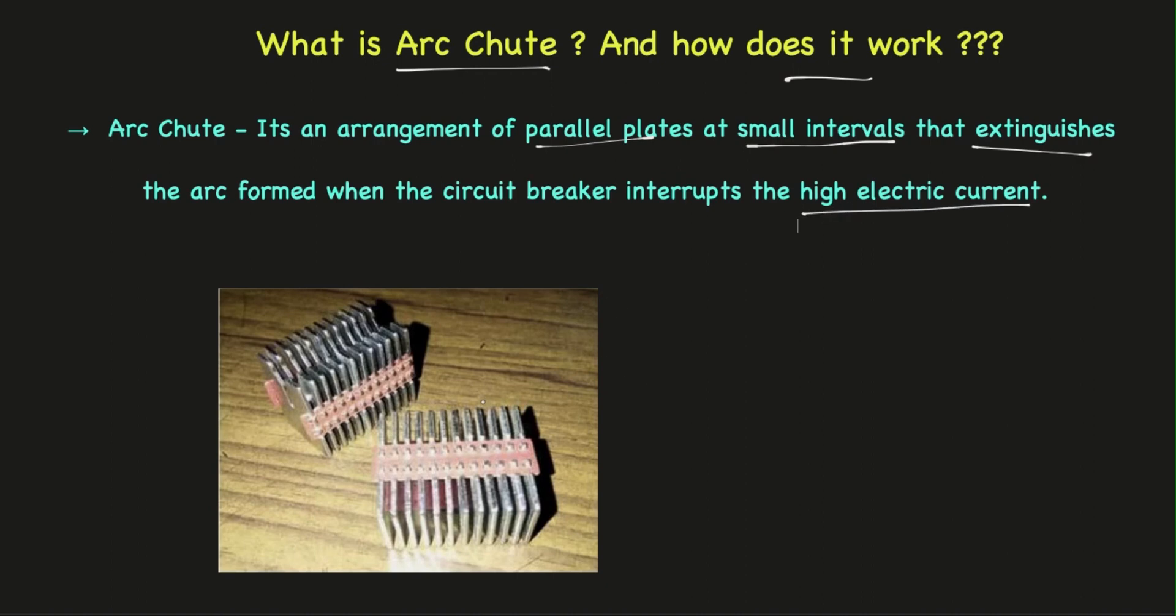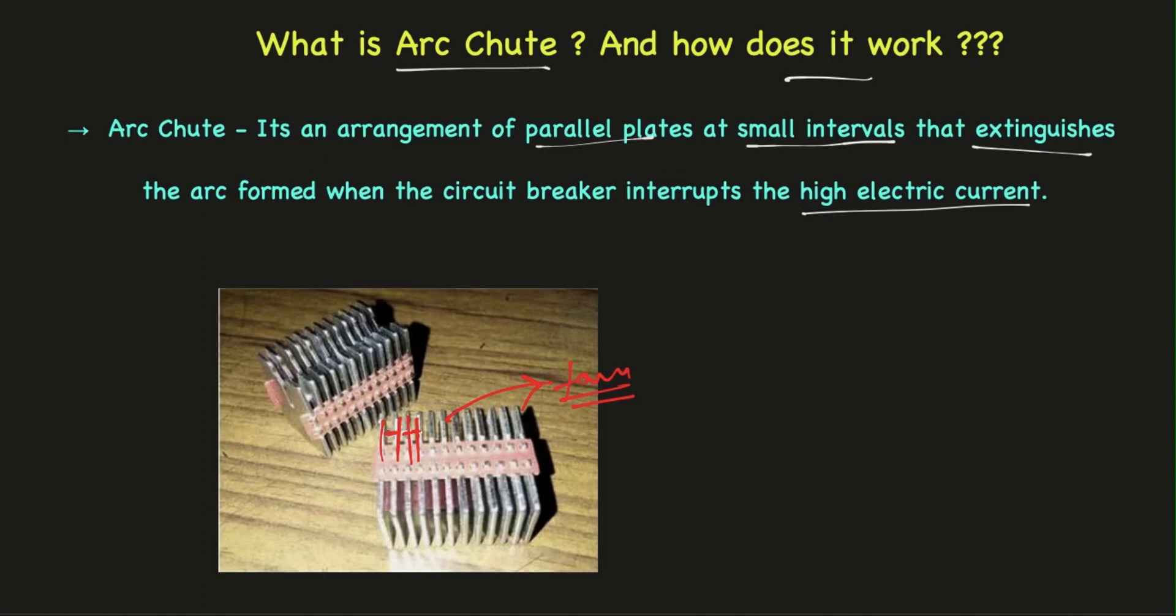This is how externally arc chutes look like. These are the small metallic plates which are separated from each other, and these metallic plates are made with ferromagnetic material so that when an arc is formed, this ferromagnetic material attracts the arc towards it, flicking the arc between these gaps.